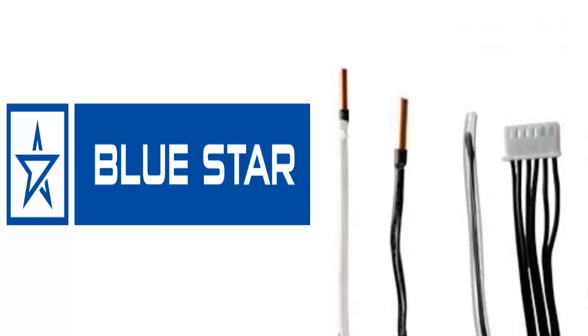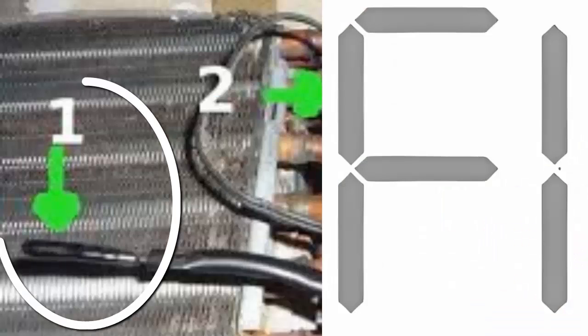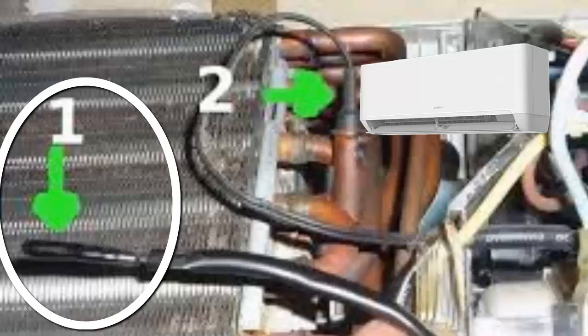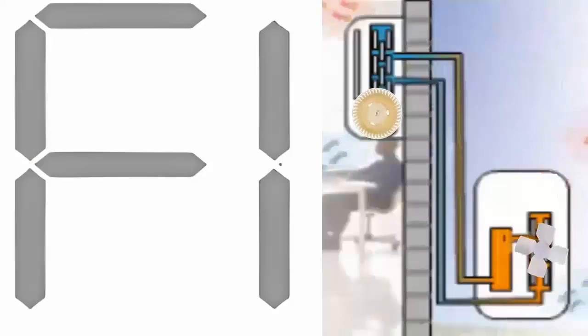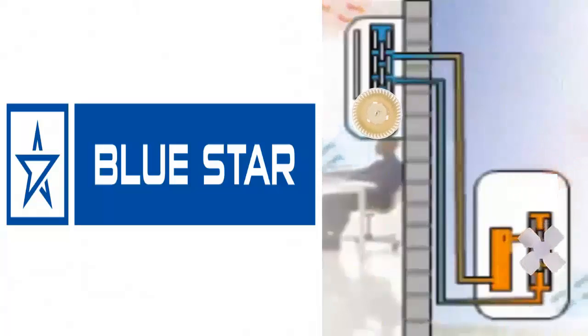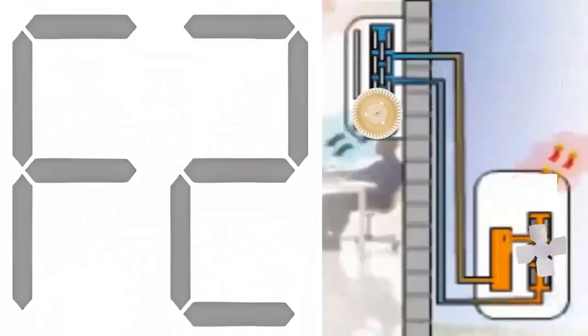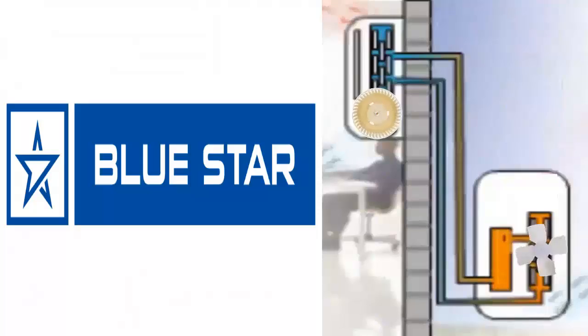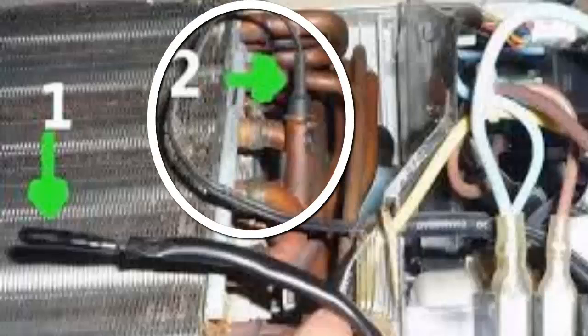Below is the most common interpretation of error codes associated with temperature sensor faults in Blue Star air conditioners. Code F1 indicates an error in the indoor ambient temperature sensor located in the indoor unit. This sensor is responsible for measuring the temperature of the air that the indoor unit's fan sucks in, with the aim of averaging the temperature of the space to be cooled. Code F2 indicates a problem with the indoor unit coil temperature sensor, which is responsible for measuring the refrigerant gas temperature in this area to prevent the coil from freezing.